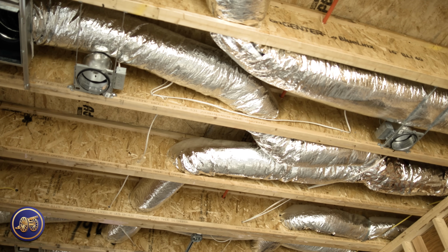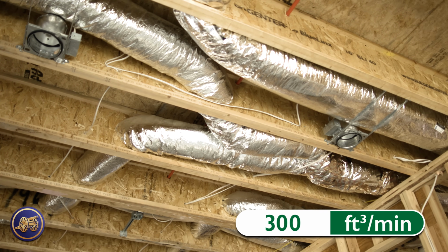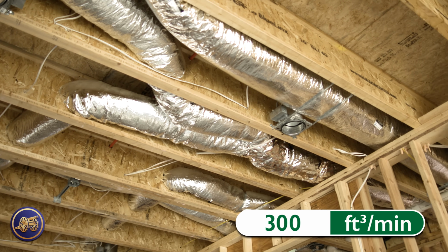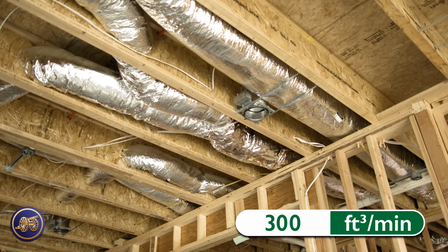If you remember as a kid at McDonald's, you'd take one of those large fat straws, stick your finger on the end, and suck hard. What happens? It collapses. The problem with flex duct, which is what we installed in the house, is that it's only rated to 300 cubic feet a minute. That rating matters even more when you're pulling air through ductwork versus pushing it. You can blow as much air through ductwork as you want without worrying about it failing, but pulling it through is a different story.